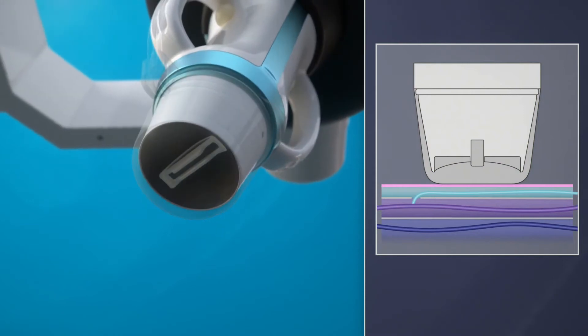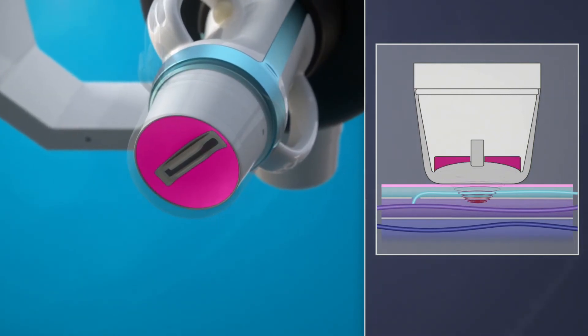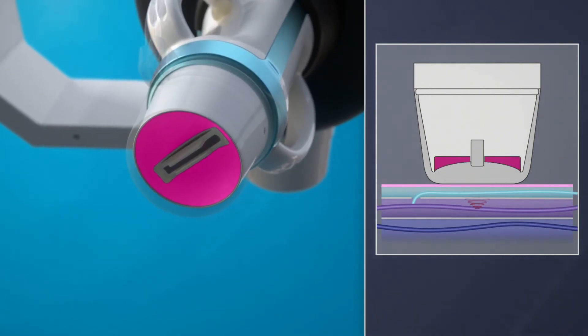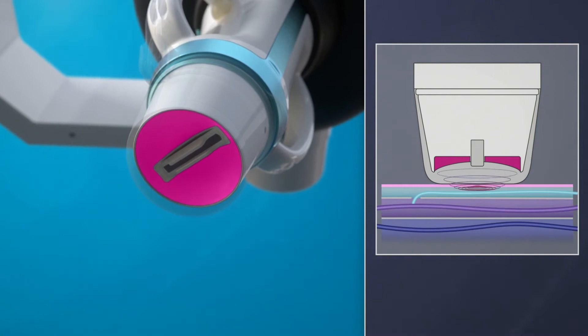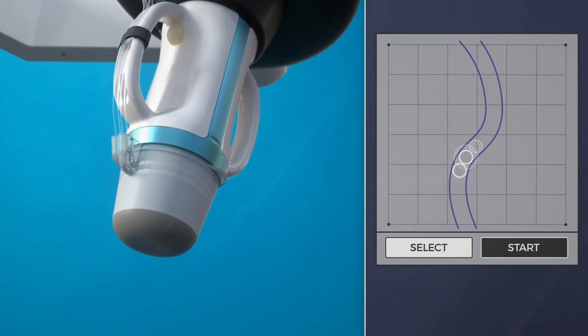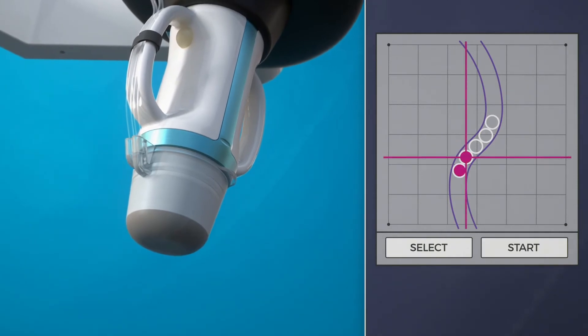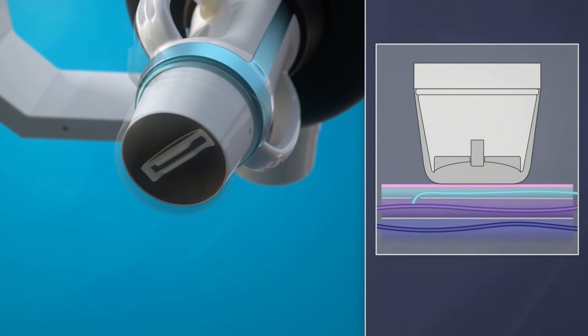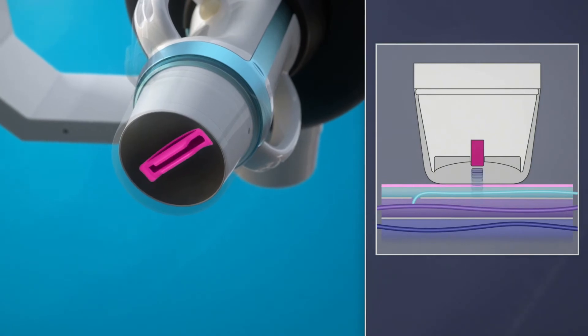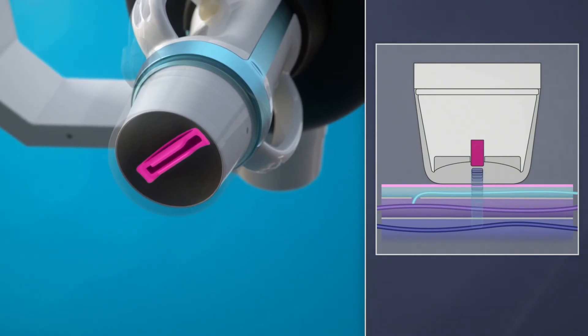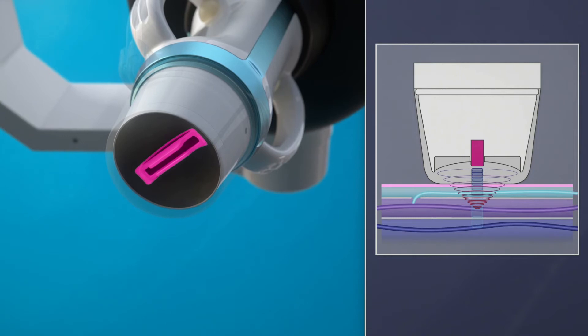During treatment, a high-intensity ultrasound beam is focused on the vein. As the thermal energy is delivered, the vein shrinks and is sealed closed, all step-by-step and automatically steered with a touch-screen monitor. An in-beam linear ultrasound probe allows visualization of the vein in real-time and ensures optimal accuracy.